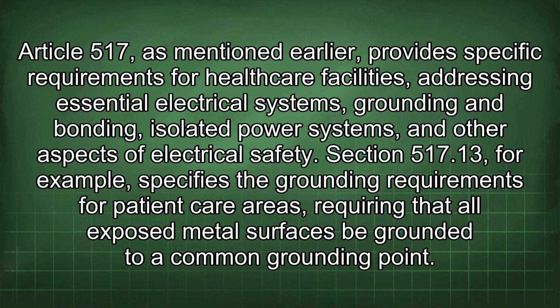Article 517, as mentioned earlier, provides specific requirements for healthcare facilities, addressing essential electrical systems, grounding and bonding, isolated power systems, and other aspects of electrical safety. Section 517.13, for example, specifies the grounding requirements for patient care areas, requiring that all exposed metal surfaces be grounded to a common grounding point.